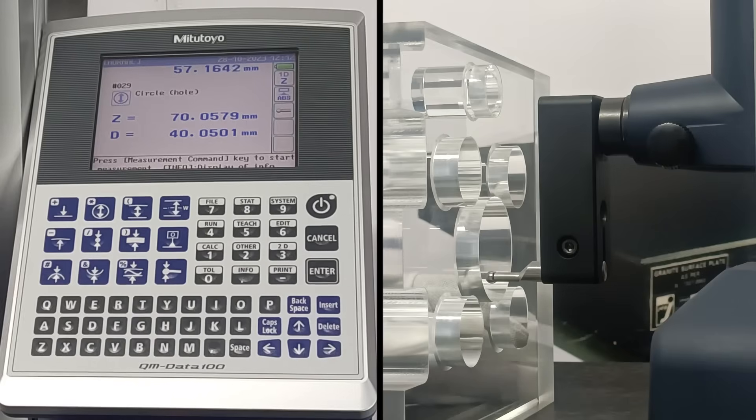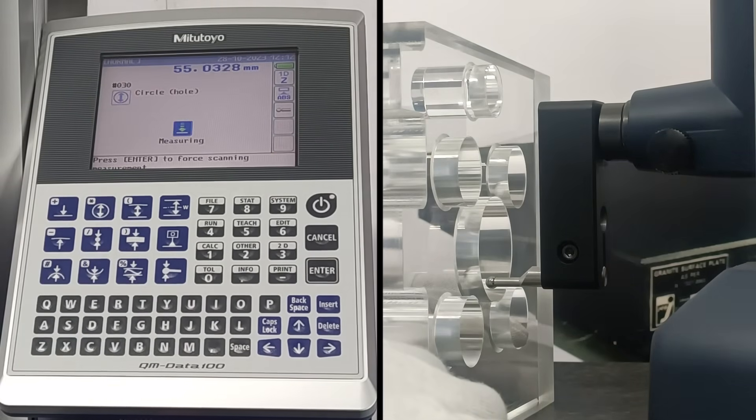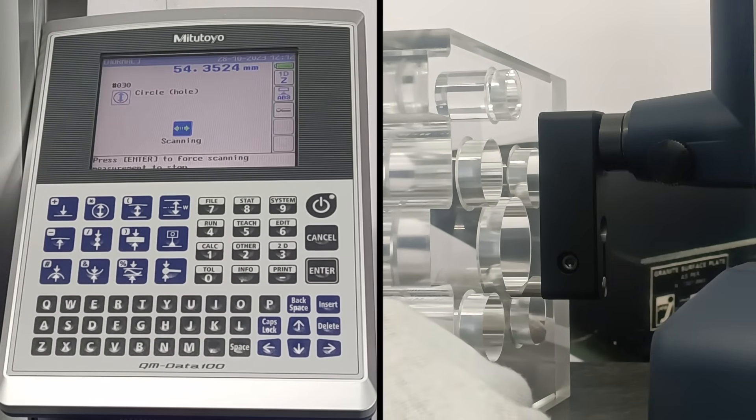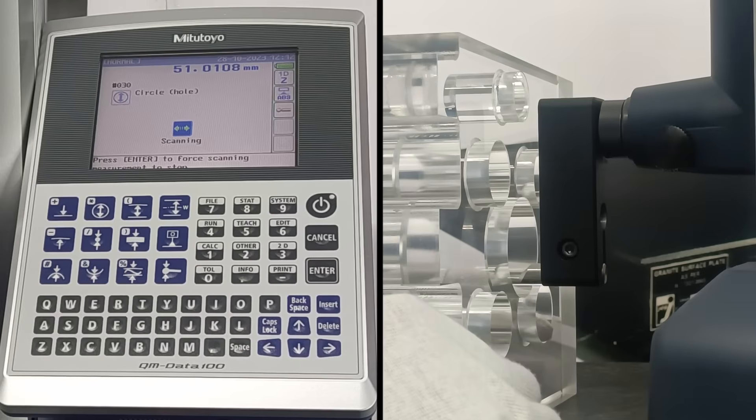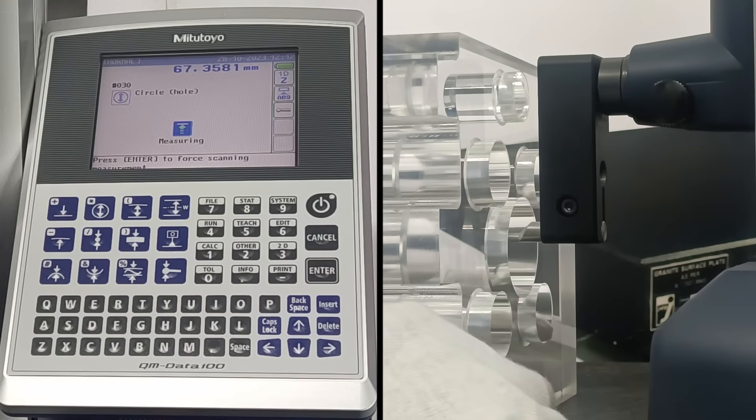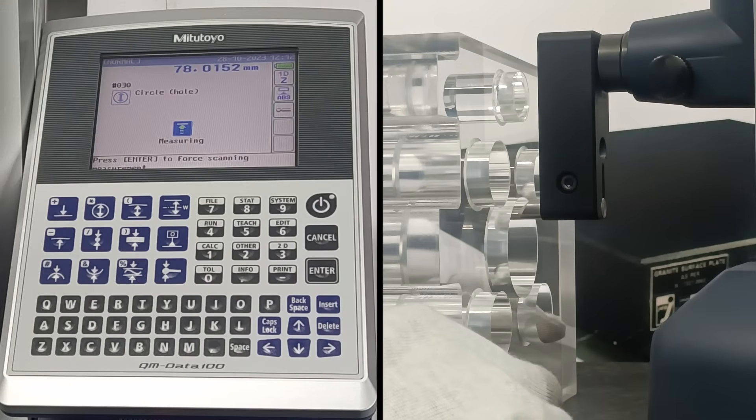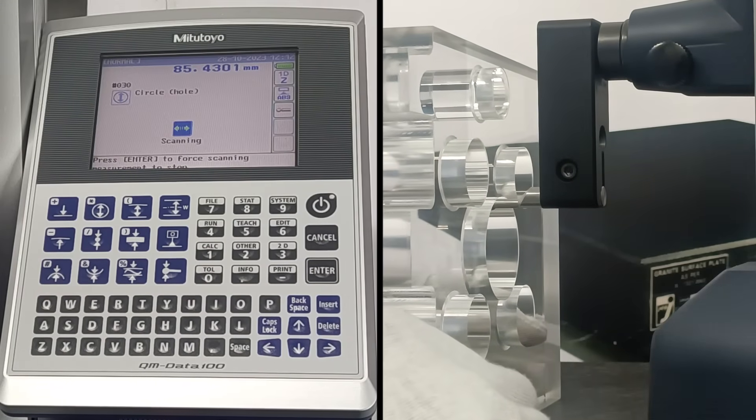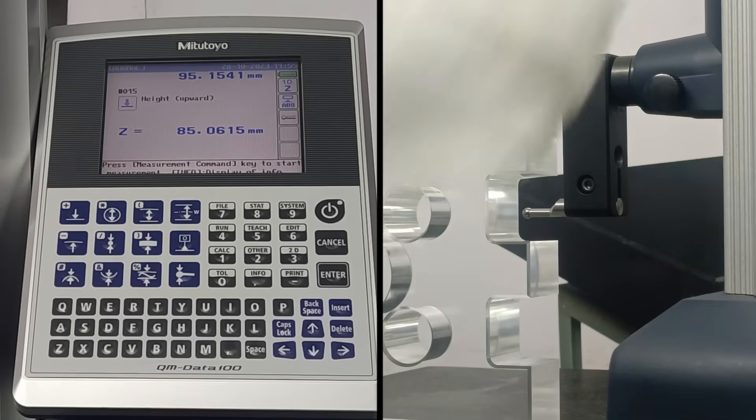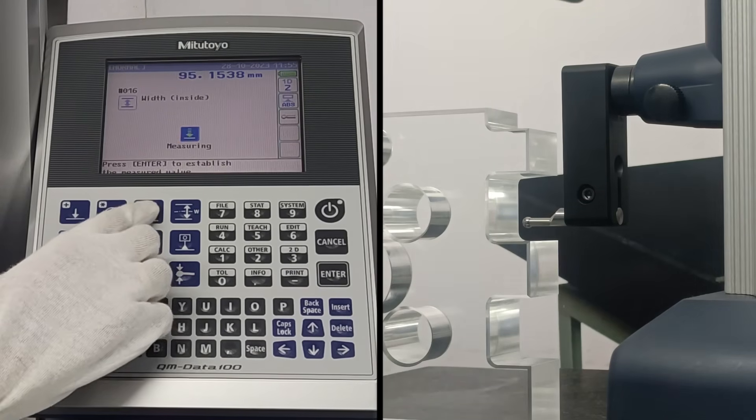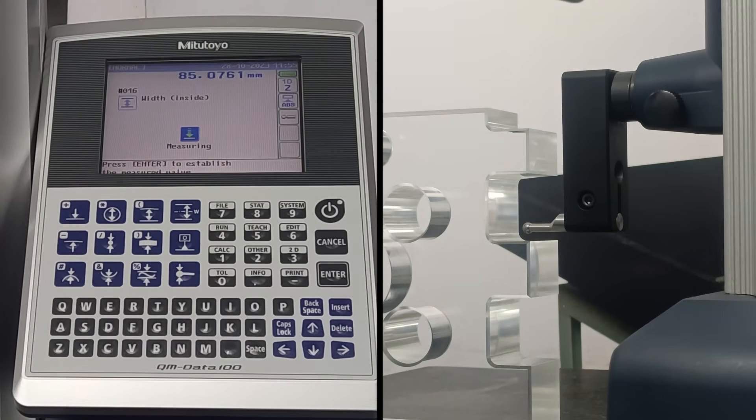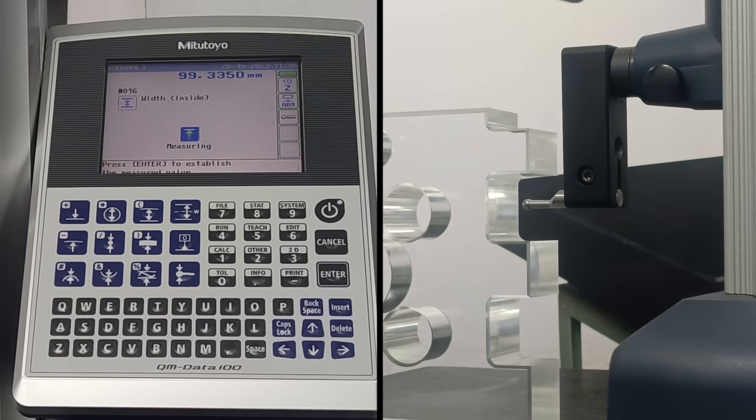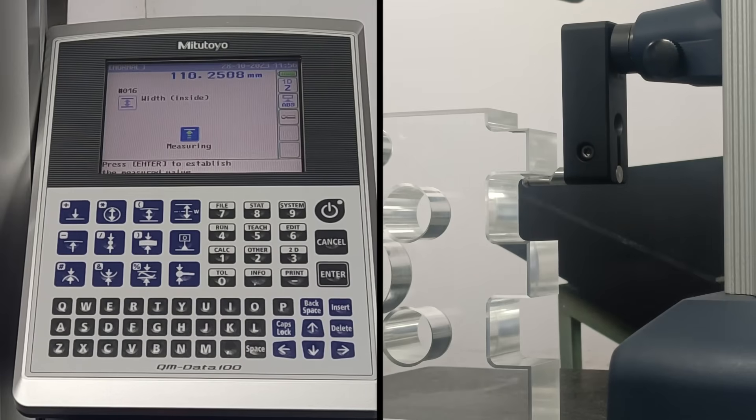This function performs scanning or tracing measurement on the bottom and top of a hole to determine the diameter. Move the workpiece or main unit to perform scanning. Z is the coordinate axis and D is the diameter. This function measures the bottom and top positions of an inside width element to determine the inside width W and the center coordinate axis Z.